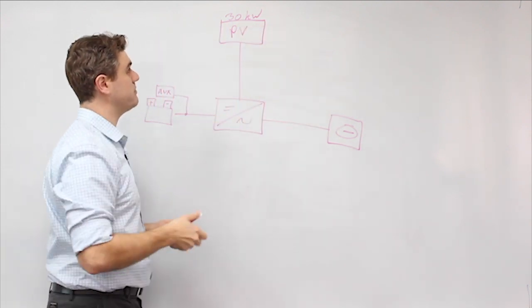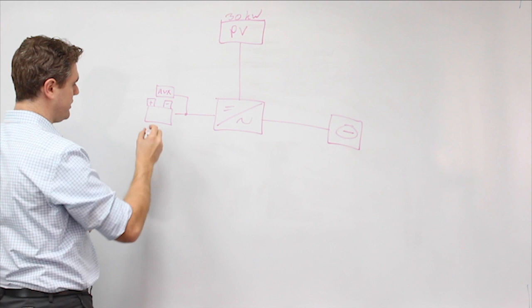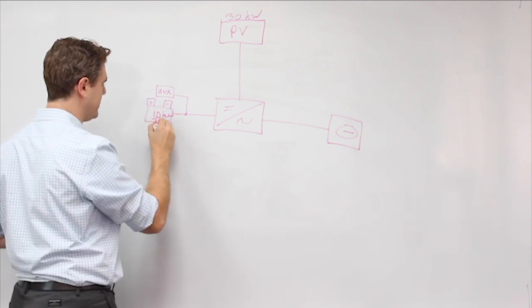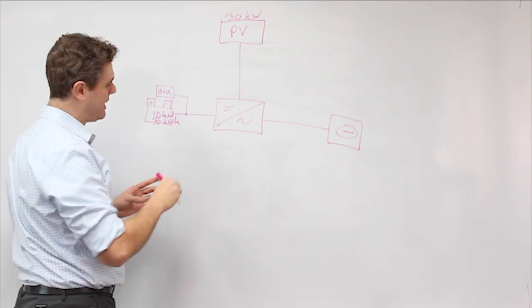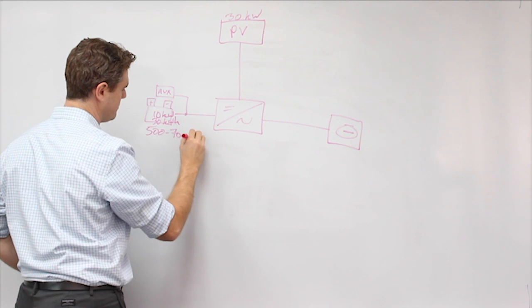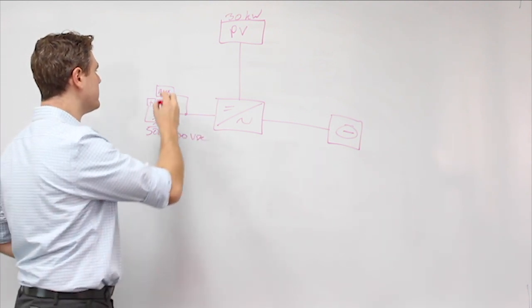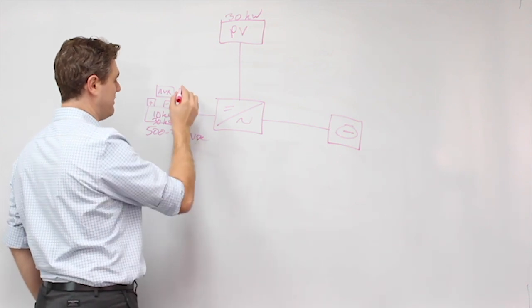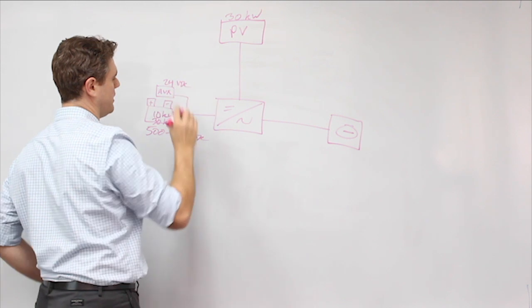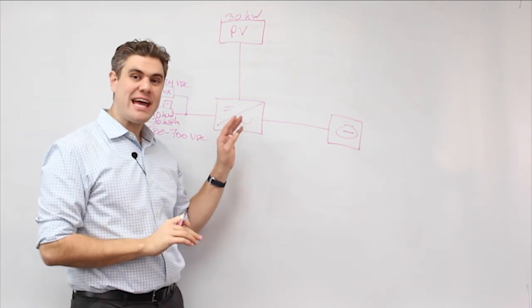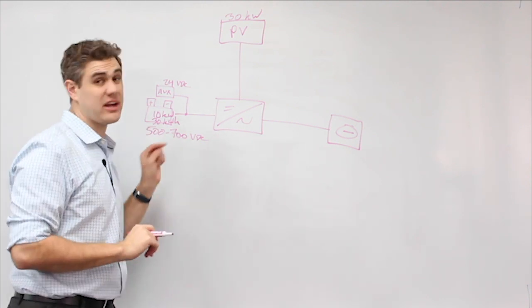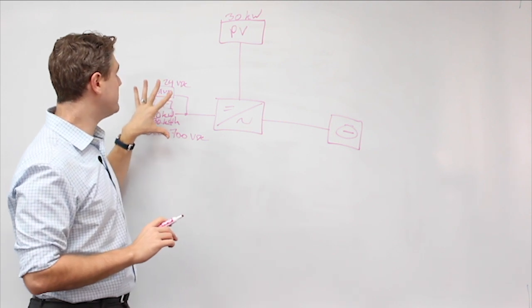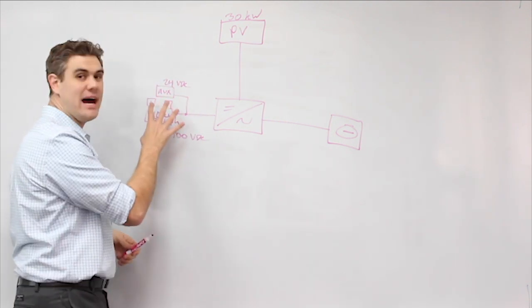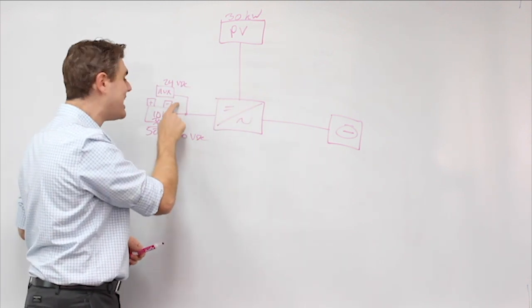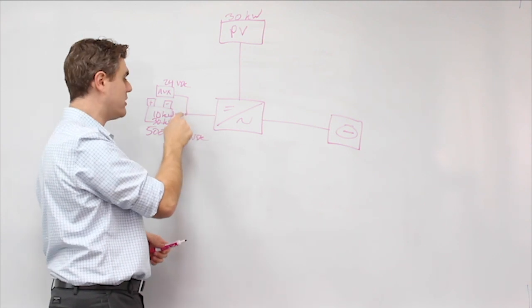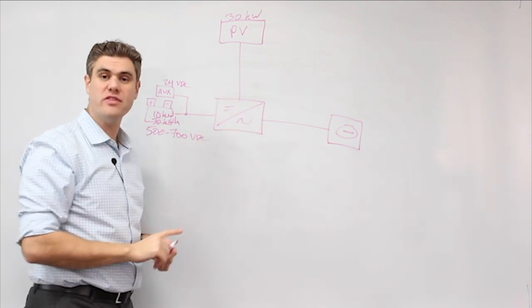But this is a DC coupled system. So, and let's just put some round numbers here. I'm going to call this a 10 kilowatt battery, call it 30 kilowatt hours. And we're going to operate this battery at 500 to 700 volts. All right, there we go. And these loads are going to operate at something lower. They don't need 500 to 700 volts, maybe call it 24 volts. All right. So notice I haven't talked about battery chemistry, battery technology, solar chemistry, solar technology. This is as broad and as general as you can get. Any type of battery and solar system that are DC coupled and that have auxiliary loads fed from the DC bus or from the battery itself fit within this model.